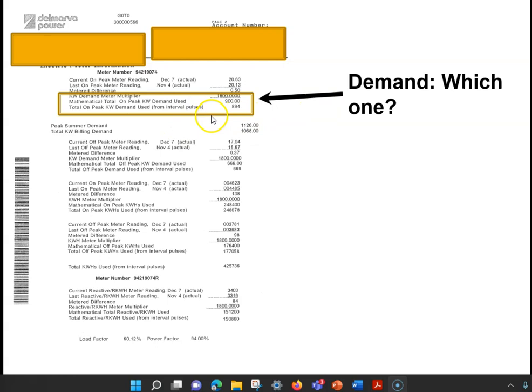So here we have two demand charges. Sometimes you only have one, sometimes you'll have two. There's usually not a discrepancy, but I think it's important to note that sometimes you do. You can see you have 900 and 894 kilowatts. Okay, so that tells you during this month, so this is the month of November through December, so this is basically November. So in that, whatever 33 days or so, these numbers are the single highest 15 minutes of power use the entire month.